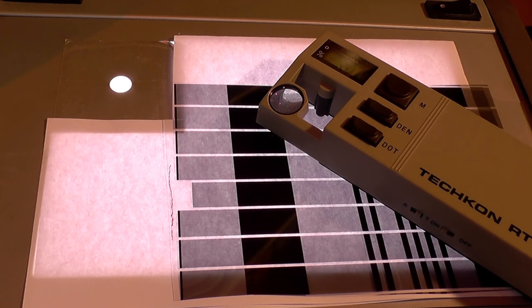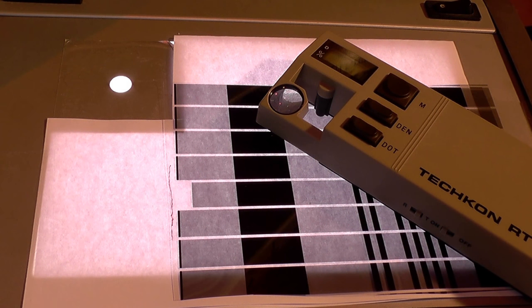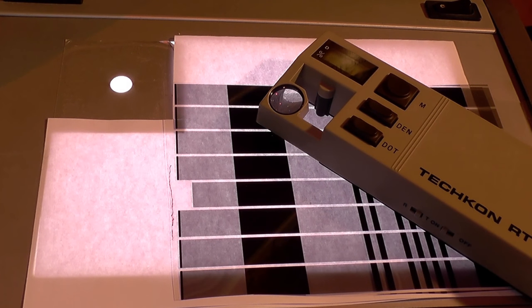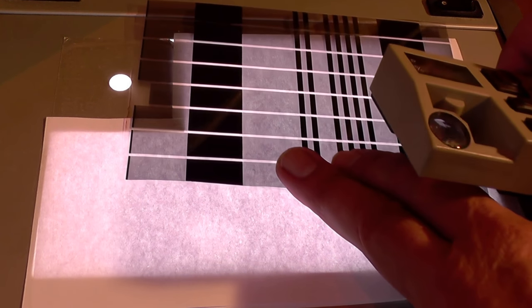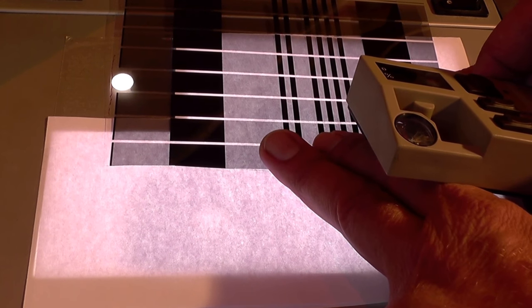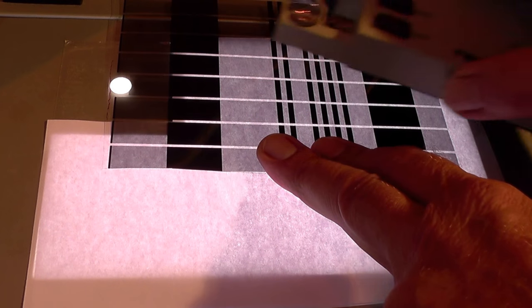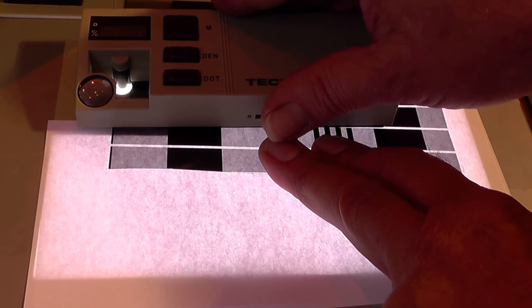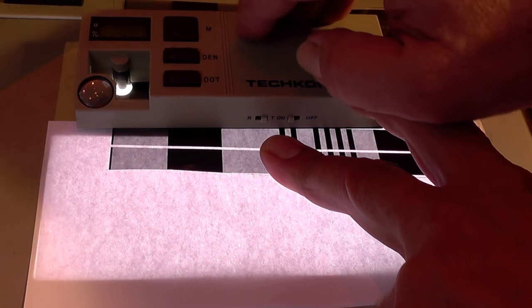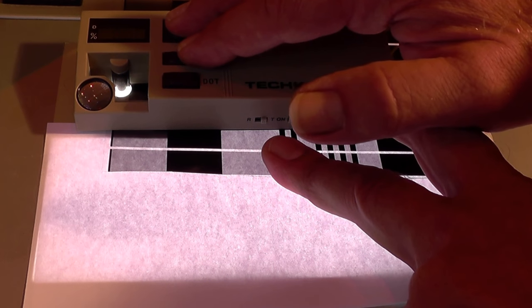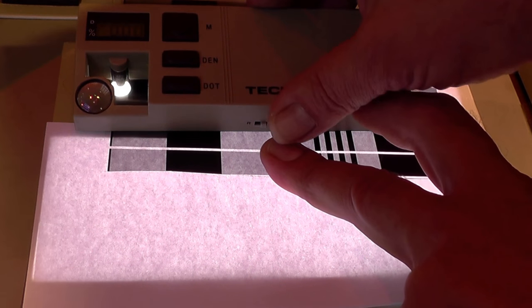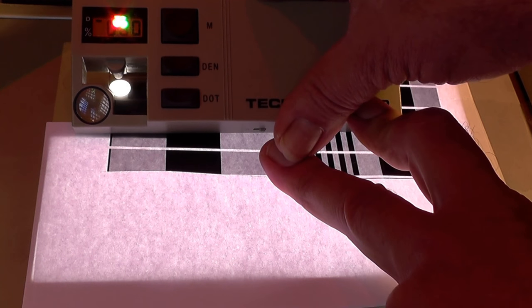Now one more video to see better the results on the densitometer. Like before, we start with the calibration - the clear part of the film over the point to measure. We measure density, both buttons, pressing C, now it's set.